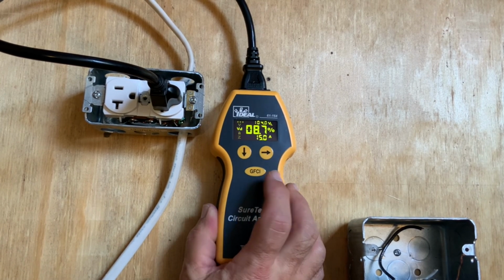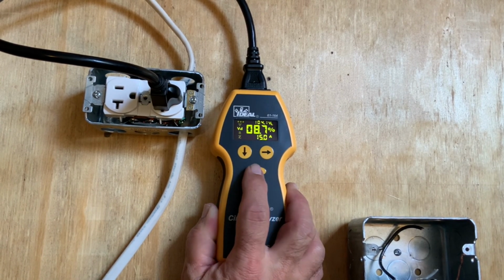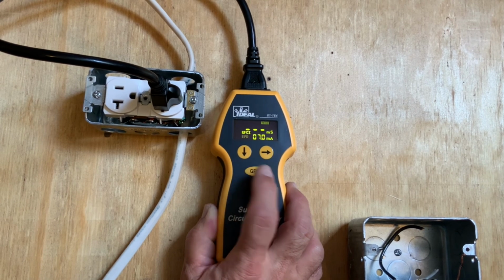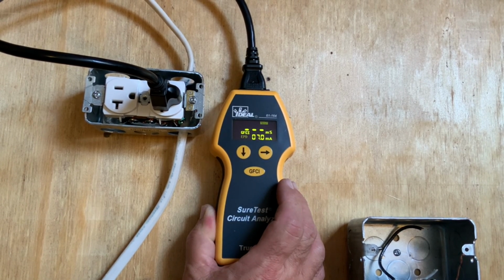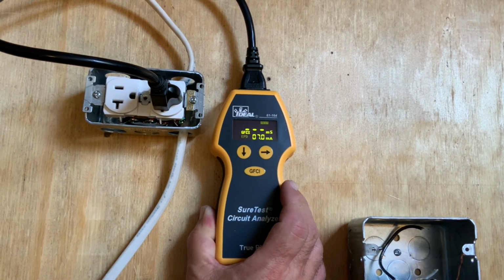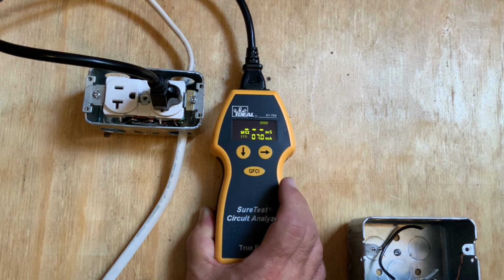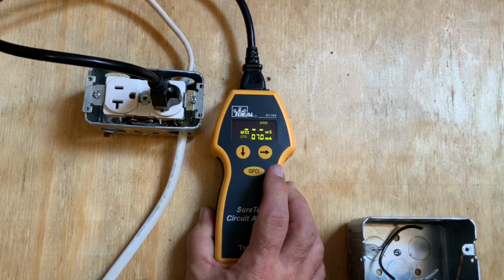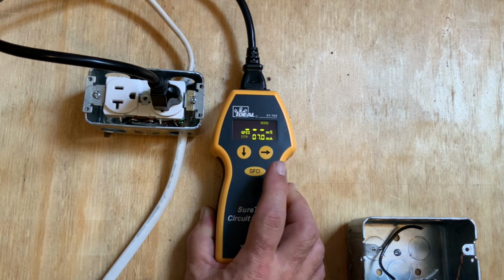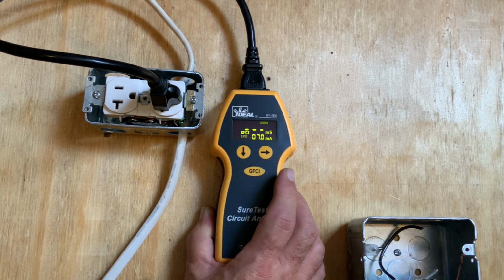From any screen on this tester, you can start a GFCI test by hitting the GFCI button. There are 2 types of GFCI tests that this can do. A 6 milliamp test, which is what you would do on your traditional outlets that you see in kitchens and bathrooms. It actually tells you what current it is going to be testing at based on the voltage coming in. Since my voltage is a little bit low right now, this is saying it's only going to do a 7 milliamp test, but that's fine for testing most outlets.